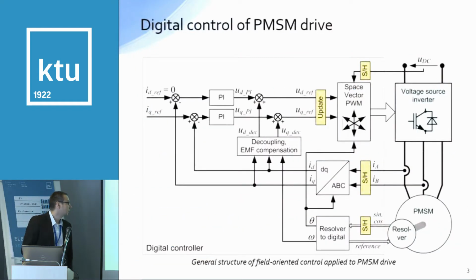Here's a typical structure of field-oriented control applied to PMSM drive. Here's the inverter, motor - some values are measured by digital controllers: DC voltage, motor phase currents, and rotor position and speed. Phase currents are transformed into DQ coordinates in order to enable the controller to easily control the motor's torque. So we have to control 2 current components: the D component is usually forced to 0, and the Q component is set according to desired torque.